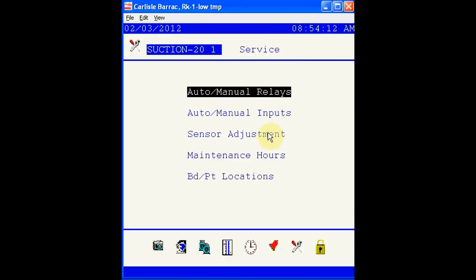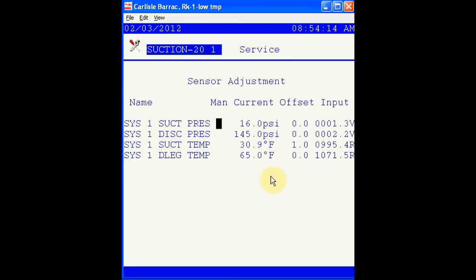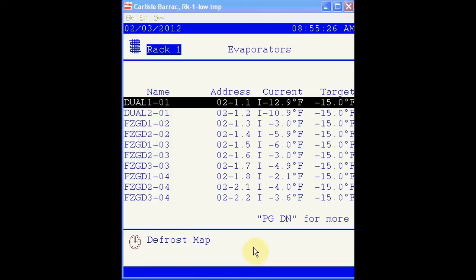Let's go to the sensor adjustment menu. Here you see several options. The current reading is displayed, any offsets are displayed, and here we see more detailed information about the sensor itself, including resistance values and DC voltages seen by the input board. Let's take a look at options available to evaporator screens. It's possible to place a case in defrost or even suspend alarms along with offsetting sensors.